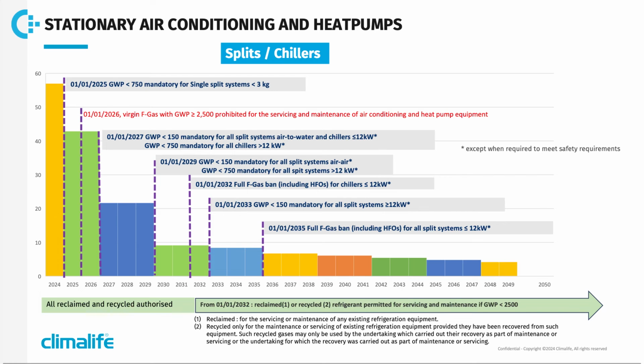In January 2032, all HFCs and HFOs will be banned for chillers up to 12 kilowatt. Moving on, we arrive at January 1st, 2033. Refrigerants with a GWP of less than 150 will become mandatory for all splits over 12 kilowatt unless there are safety requirements. And finally, on January 1st, 2035, all HFCs and HFOs will be banned for splits of up to 12 kilowatt. After January 1st, 2032, reclaimed refrigerant will continue to be used for servicing and maintenance if the GWP is less than 2,500.